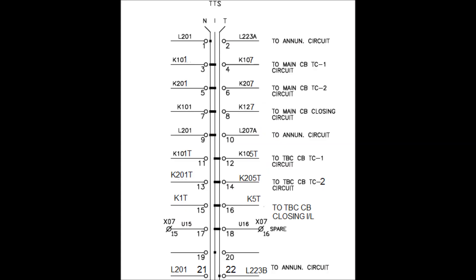The contact distribution for the NIT switch has been shown in this figure. For Normal position, contacts one and two are taken for the annunciation circuit. For Normal-Inter position, contacts three and four are taken for the main CB TC1 circuit. Contacts five and six for Normal-Inter position are taken for the main CB TC2 circuit, and seven and eight for Normal-Inter position are taken for the main CB closing interlock circuit. Contacts nine and ten are taken for the annunciation circuit.